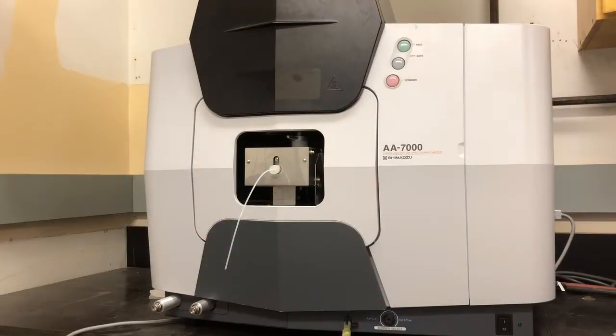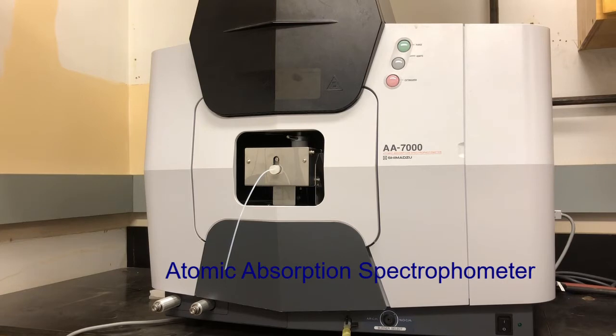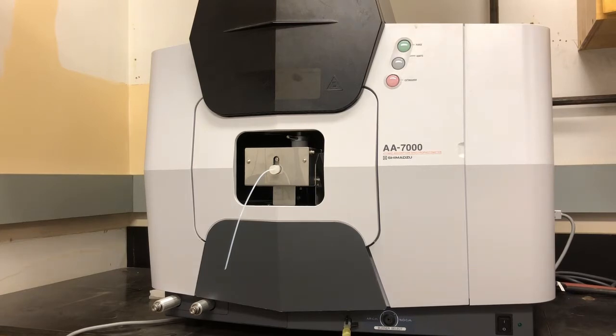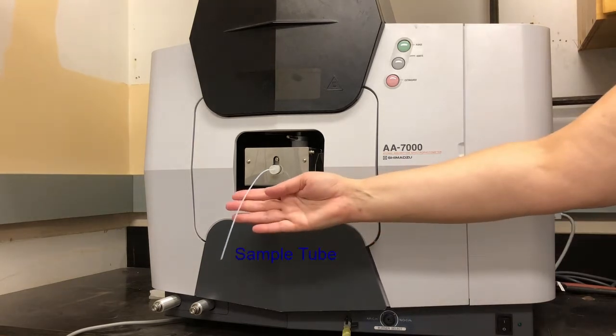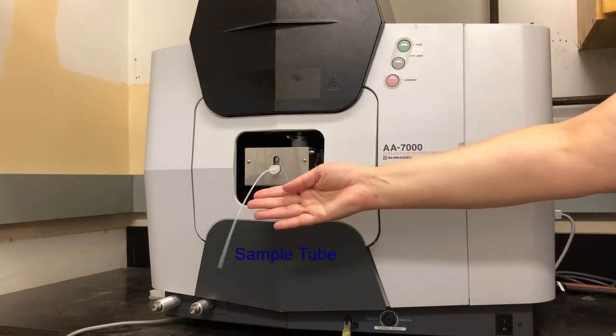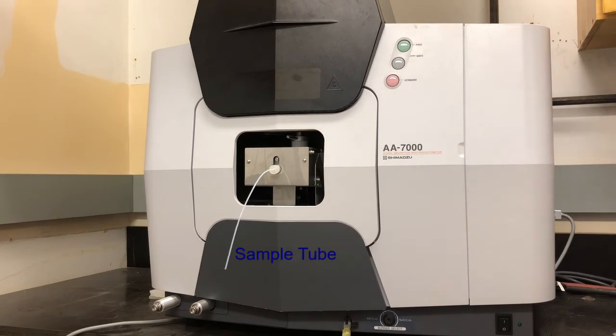This is the atomic absorption spectrophotometer. This is the AA7000 model made by Shimadzu. So I just want to show you the instrument and point out some of its main components. So the first thing we need to know is how to get the sample into the instrument. So the sample enters via the sample tube right here. This is very delicate, so you want to be very careful when handling it.